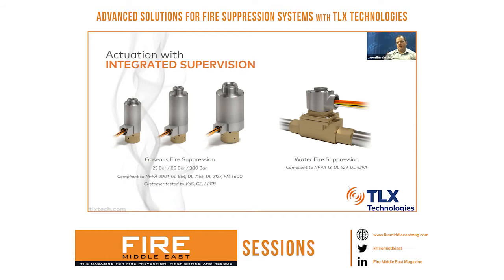or UL 864 guidelines, it came to our attention that there was a number of incidences in which, when these devices are removed from the system, there is an opportunity for the maintenance or installation personnel to have either not replaced the actuator fully or not actually replaced the actuator at all. Well, considering that that is the device that actuates the system once there's a signal from the control panel, if these actuators are not securely fastened back onto the system, it renders the system useless. So the NFPA 2001 committee stated that they needed to do something about that.